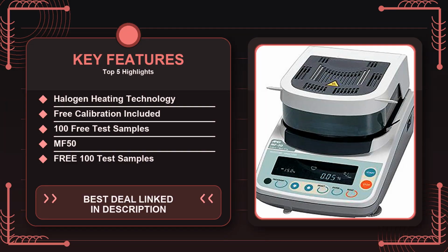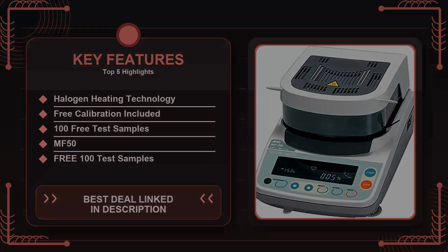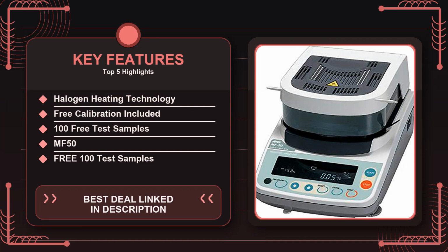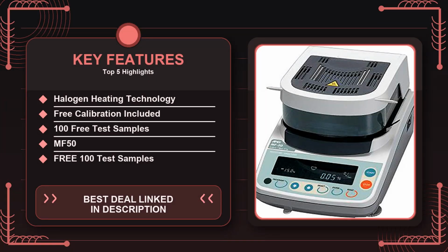On the downside, there are a couple of trade-offs you should be aware of. Because the heating element is halogen, it reaches the target temperature quickly but can be a bit finicky with samples that have very high volatile content. In those cases, the moisture can evaporate faster than the sensor can record, leading to a slight underreporting of water content. The workaround is to run a longer drying cycle or to use the pre-dry step that the software offers, which adds a few extra minutes to the overall test time.